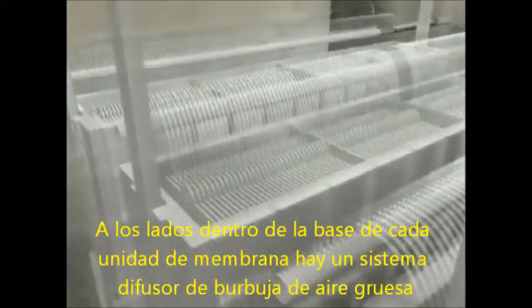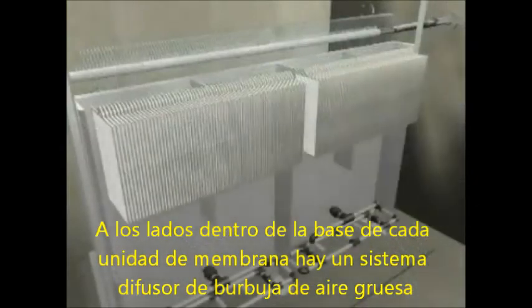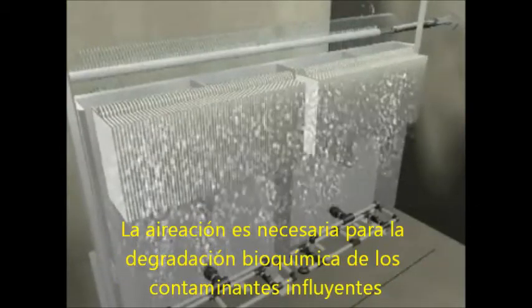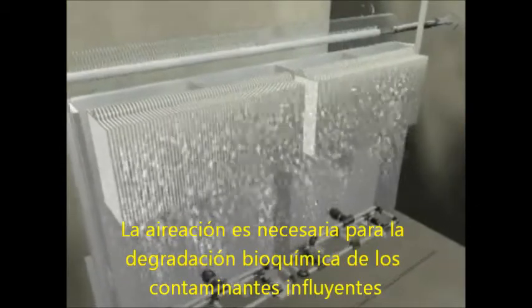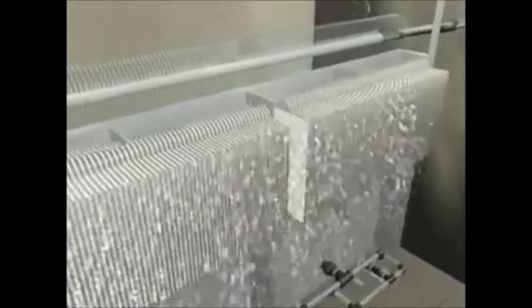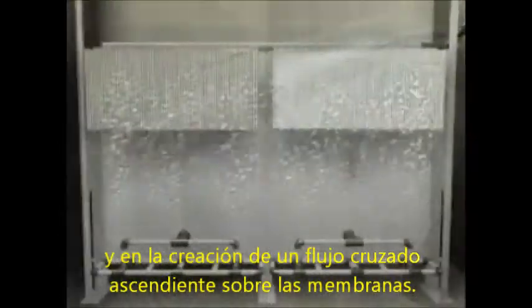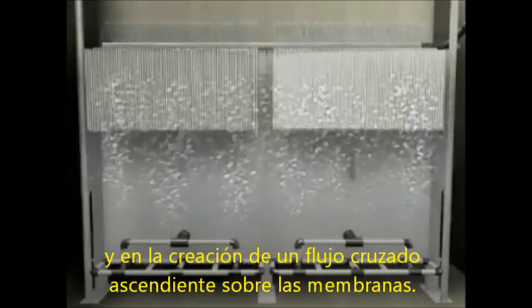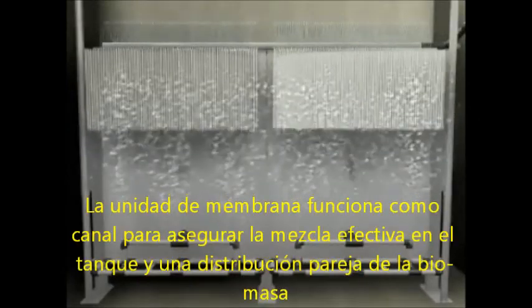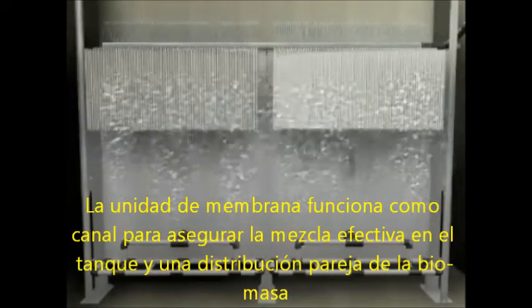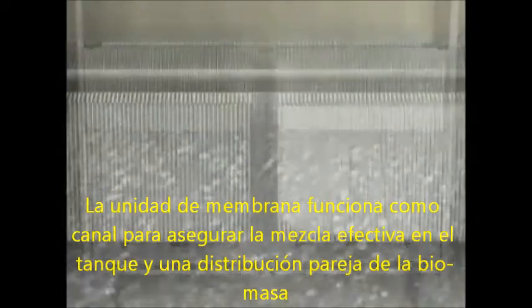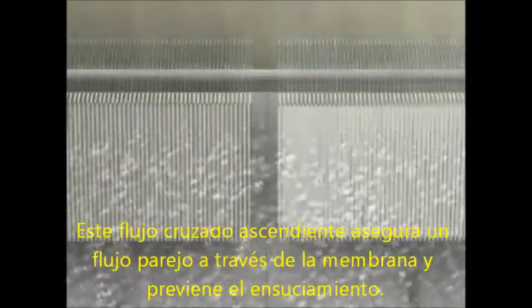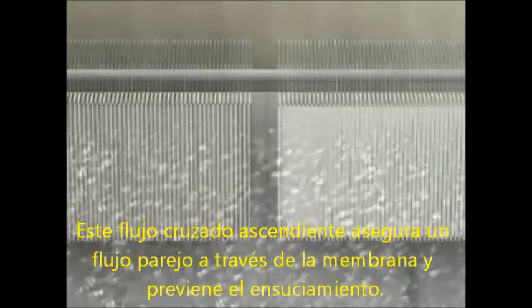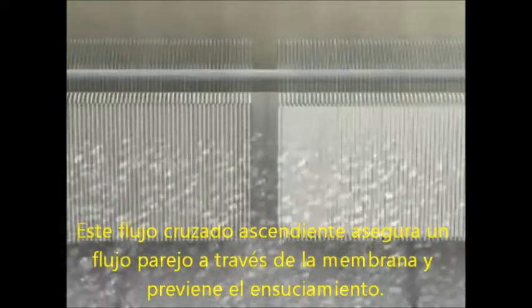Sited within the base of each membrane unit is a coarse bubble air diffuser system. Aeration is necessary for the biochemical degradation of influent pollutants and in creating an upward crossflow over the membranes. The membrane units serve as a flume to ensure effective tank mixing and even distribution of the biomass. This upward crossflow ensures an even flow across the membranes and prevents fouling.